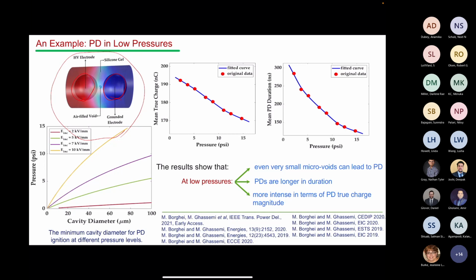The results are very exciting: they show the minimum cavity diameter that can cause PD at different pressure levels. This is the pressure, and this shows the electric field at which PD starts for each case. You can see that as the pressure drops, the size of these trouble-making voids shrinks.